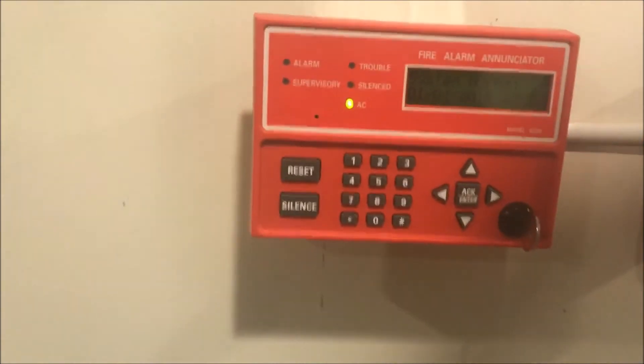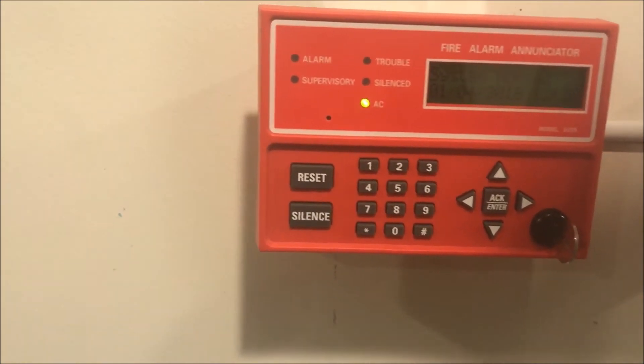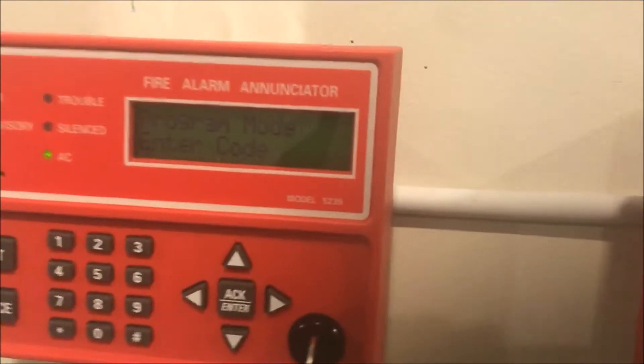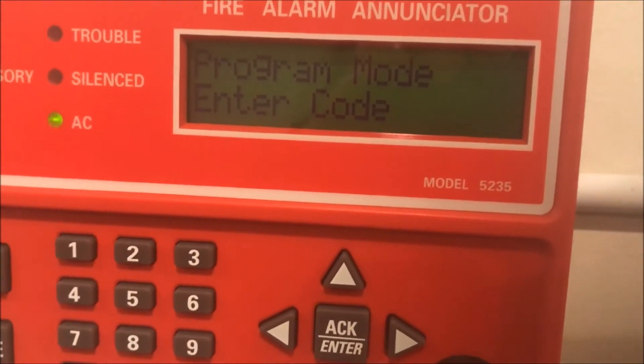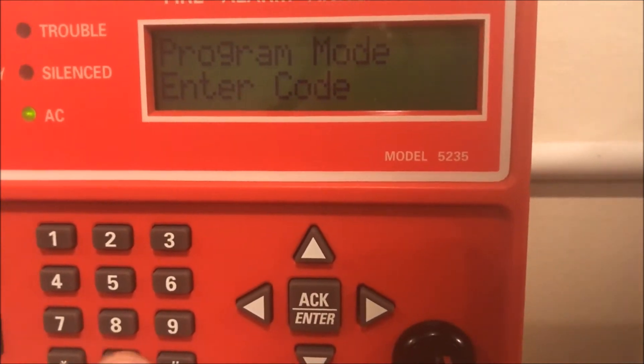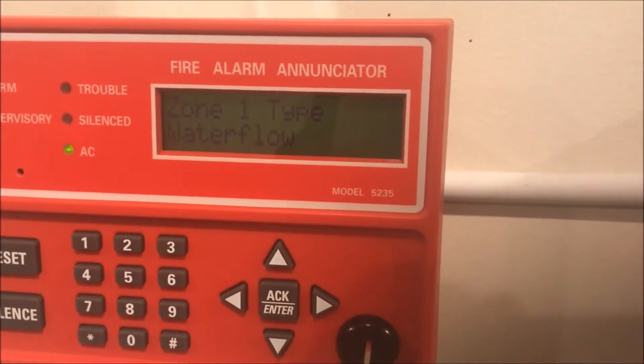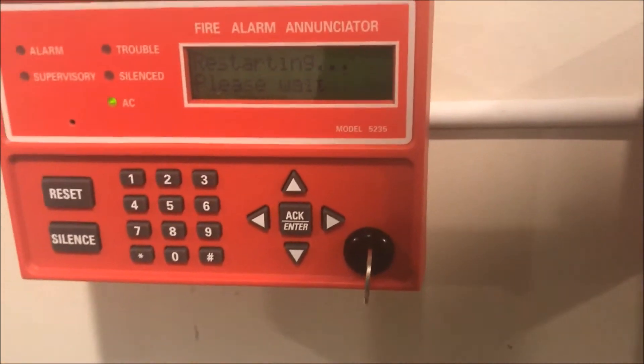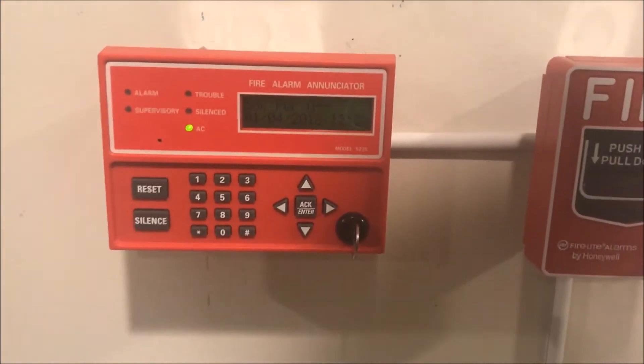So here's the annunciator. This one actually has a different tone than the panel, which I like — it's a better sounding beep. We are going to enter into programming settings. Now we are in program mode. We are going to change zone 1 type from a fire alarm to a water flow alarm. We'll hit enter and then reset. If you listen closely, you'll be able to hear the panel click and reset. Hear that beep and that click? That's the panel resetting — it does it from the enunciator. The panel is now booting up.